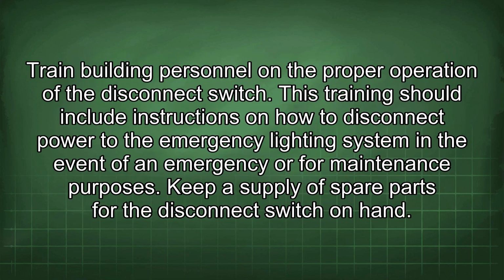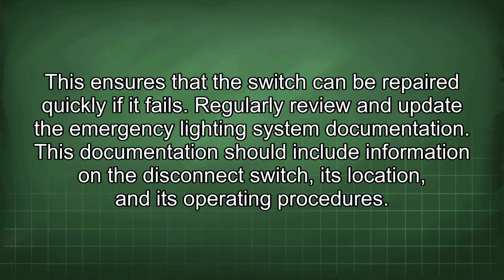Train building personnel in the proper operation of the disconnect switch. This training should include instructions on how to disconnect power to the emergency lighting system in the event of an emergency or for maintenance purposes. Keep a supply of spare parts for the disconnect switch on hand. This ensures that the switch can be repaired quickly if it fails. Regularly review and update the emergency lighting system documentation. This documentation should include information on the disconnect switch, its location, and its operating procedures.